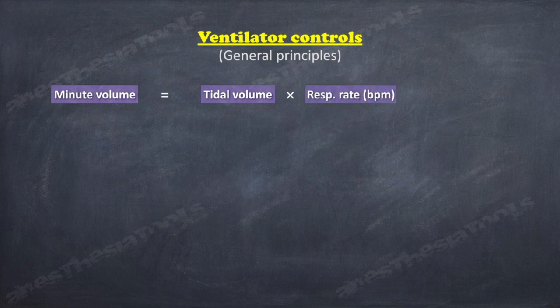Now some general principles on how to set a ventilator. The three variables involved in ventilatory parameters are traditionally arranged in the simple equation: minute volume equals tidal volume times rate, that is breaths per minute. Armed with this equation, a user should be able to switch on and set up any ventilator in its basic mode.